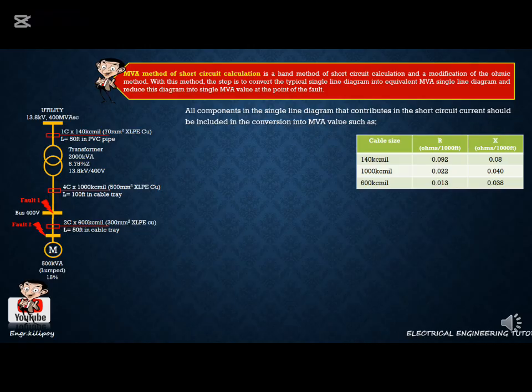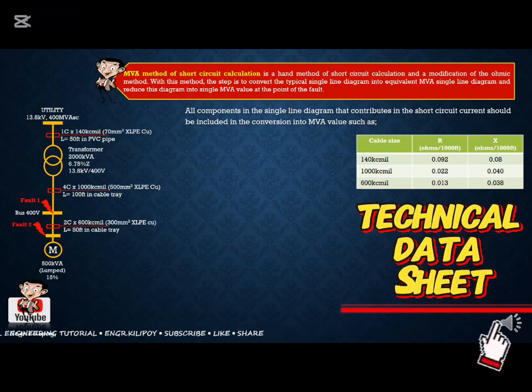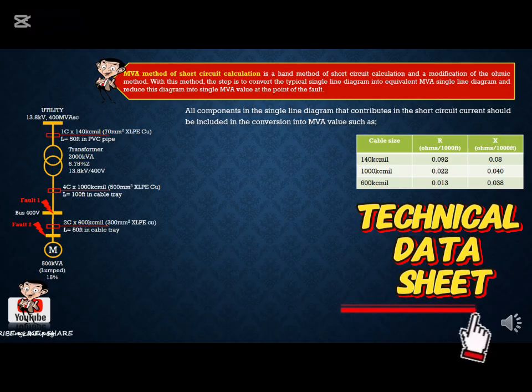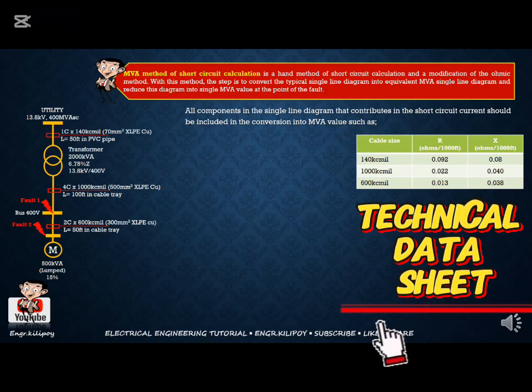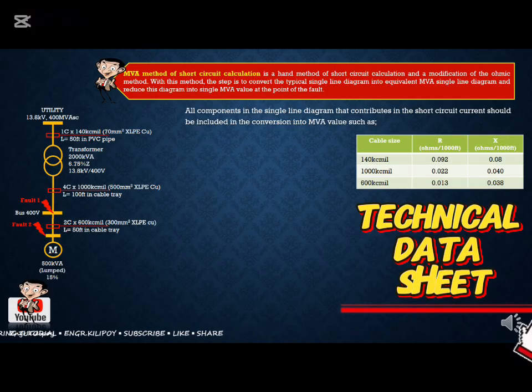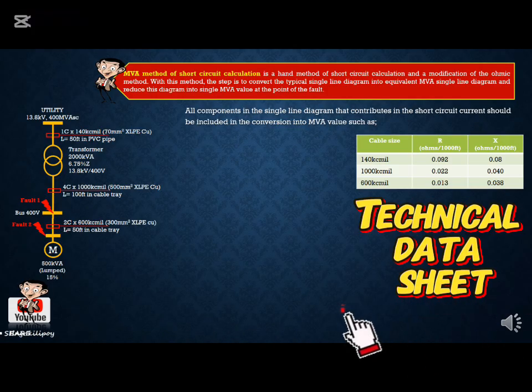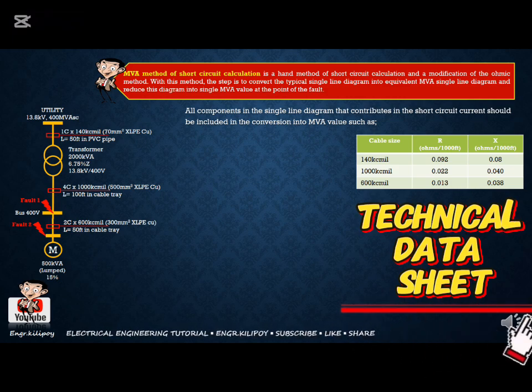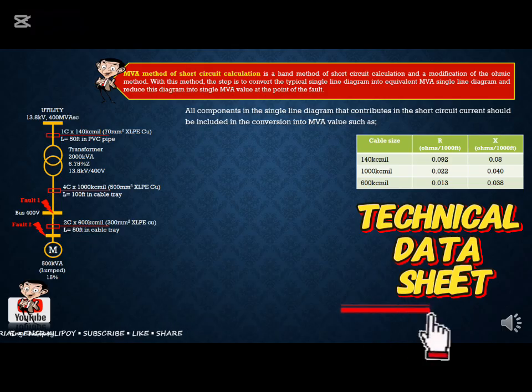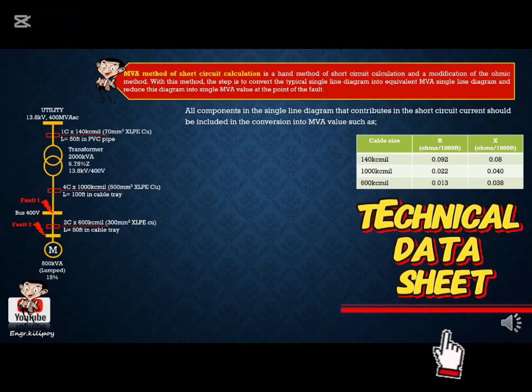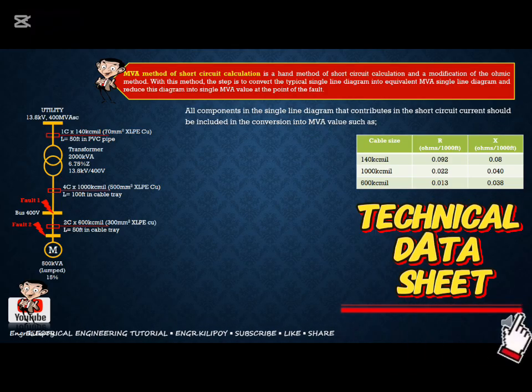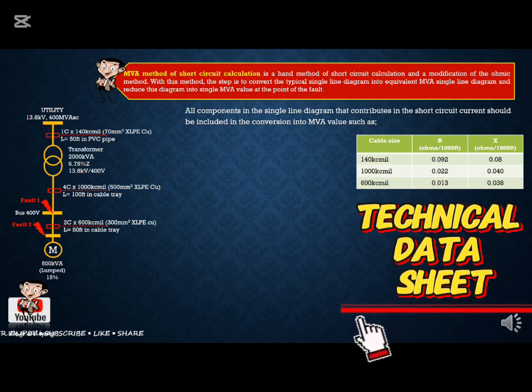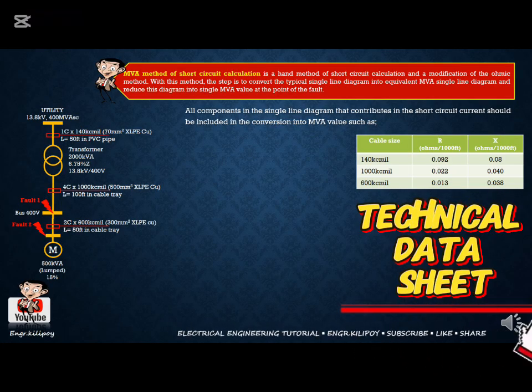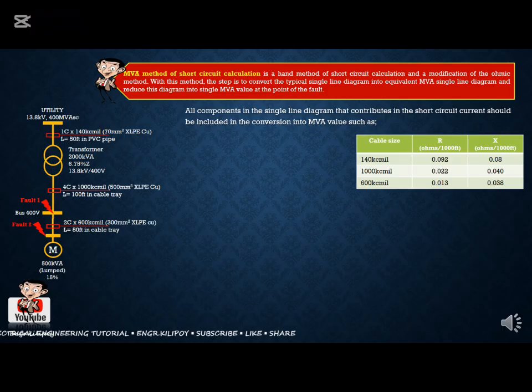Paano ba yan? So ang given natin dito, kinuha natin yung technical data sheets ng cable per size. We have 140 kcmil, 1000 kcmil, and 600 kcmil. So this technical data sheets give resistance values in ohms per 1000 feet: 0.092, 0.022, and 0.013. For the reactance value, ohms per 1000 feet, for 140 kcmil meron tayong 0.08, for 1000 kcmil 0.04, and for 600 kcmil we have 0.038 ohms per 1000 feet. So paano ba kina-compute yung impedance per phase?